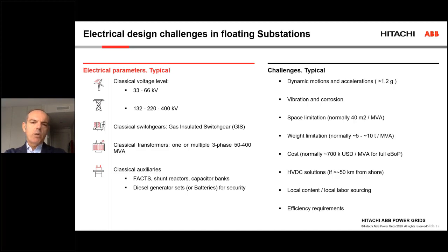For the evacuation power for the export cable, we typically talk about between 132 kV and 400. Due to the sizing requirements in floating substations, we use GIS, gas insulated switchgear, and classical power transformers from 50 to 400 MVAs. Due to the length of the cable, etc., we need compensation devices such as FACTS, shunt reactors, or capacitor banks, together with auxiliary services like gensets or batteries for backup power.